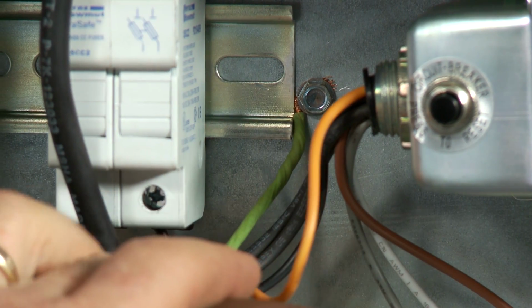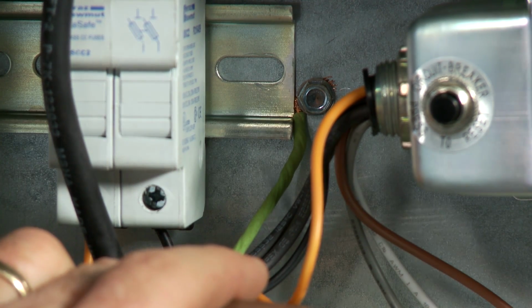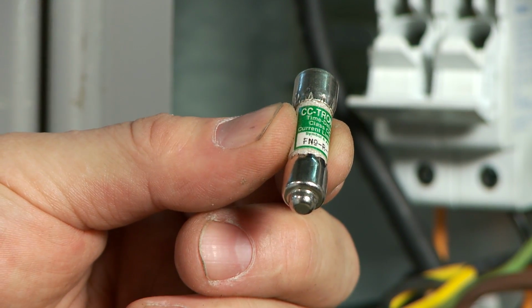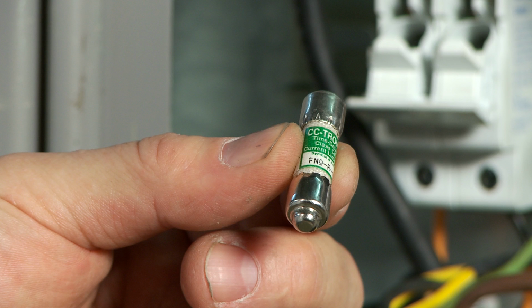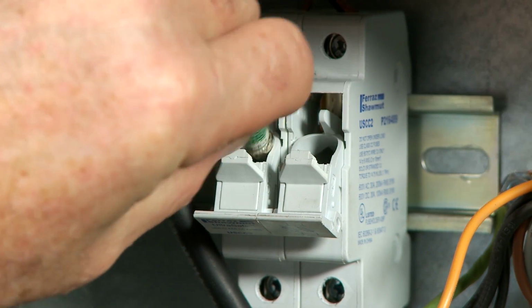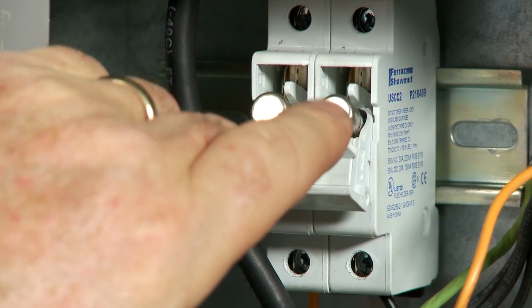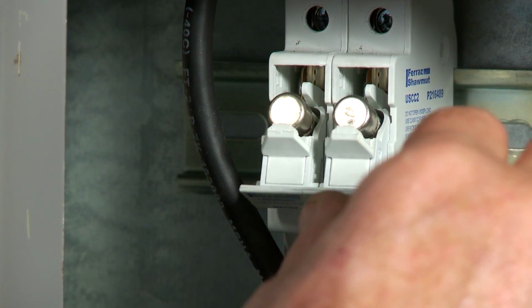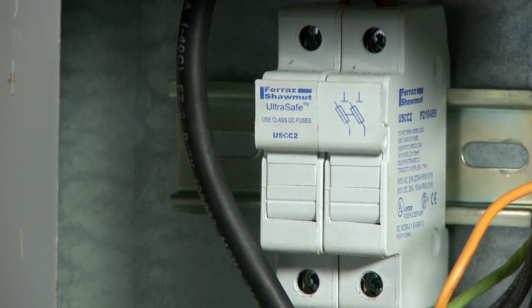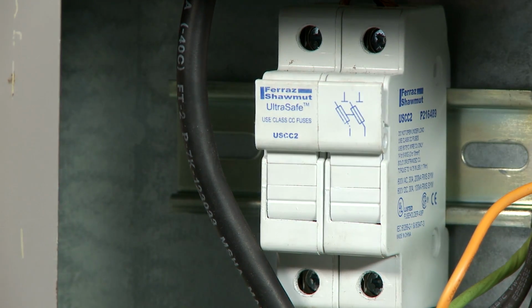Terminate the green wire on the cabinet backplate, which serves as the chassis ground. The included fuses are intended for 460 and 480 volt protection, and if other voltages are used, you will need to supply your own fuses. Ensure the fuses are installed with the dimpled end down into the fuse block. Fully close the fuse block and check all connections by lightly tugging on each wire connection to ensure they are secure.